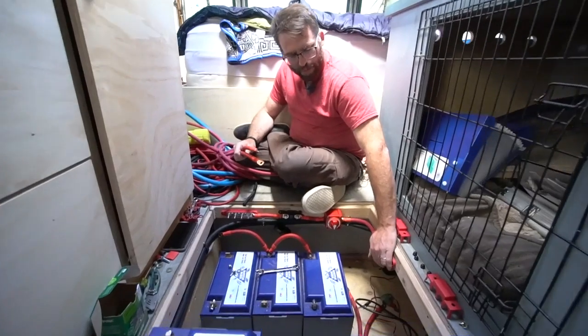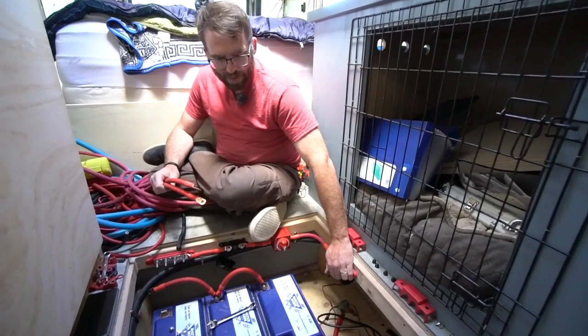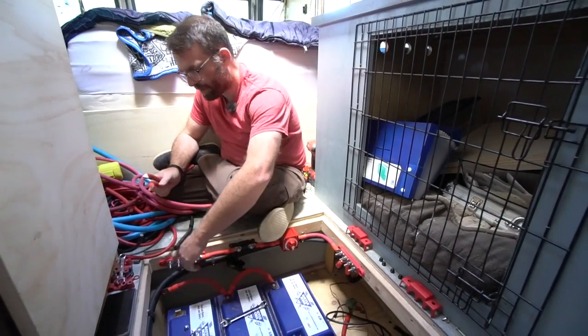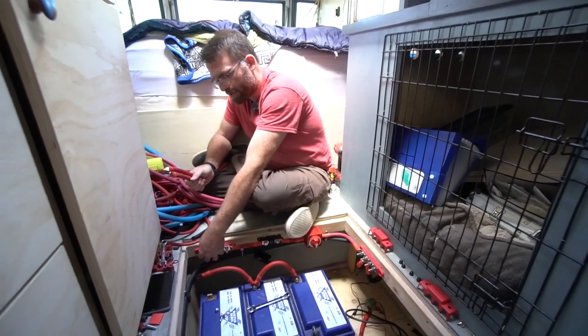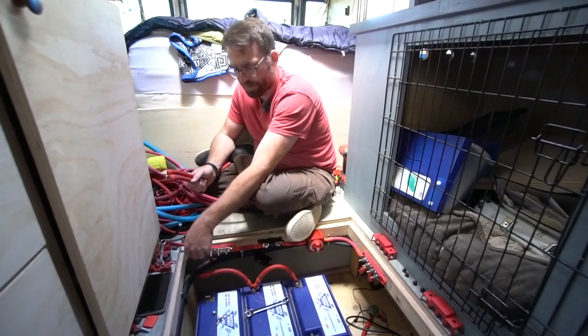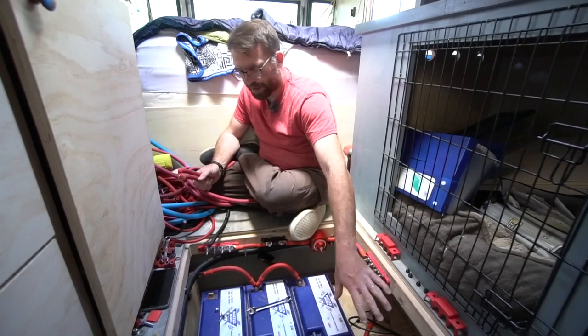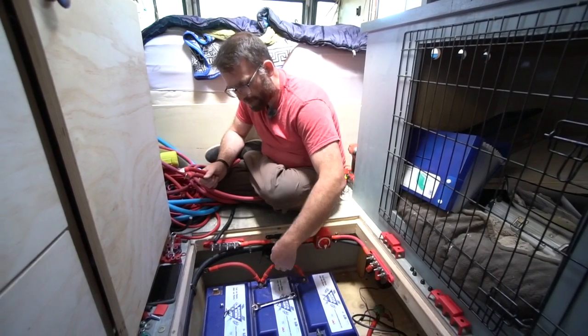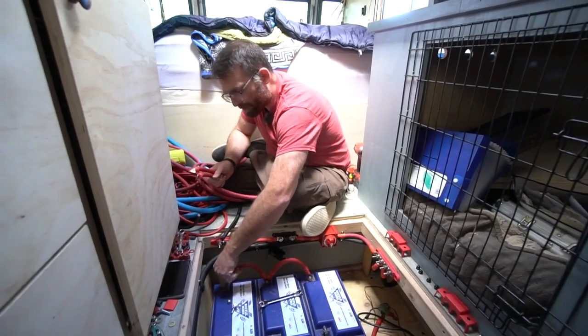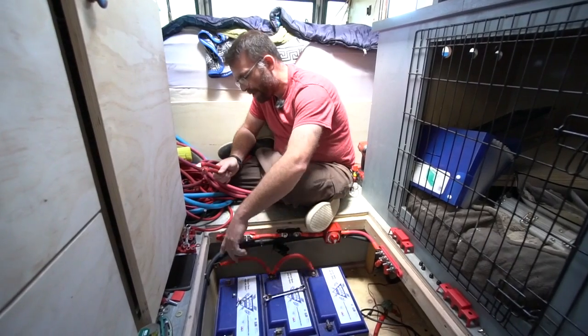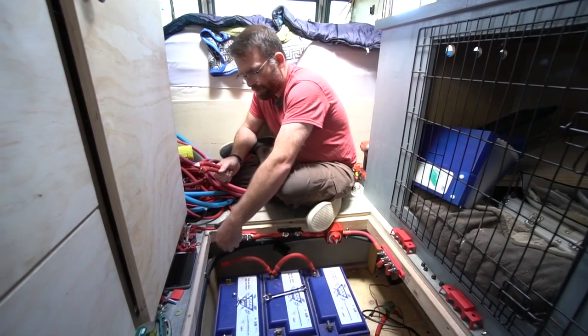This is where all of the power consumers will go. This would be the load, and this is the line side over here. These terminals are going to receive the strings of batteries off of the pack here. As I wire these up, it only takes 2 jumper cables to connect 3 batteries, but that last one off the end has to route around and connect to here.